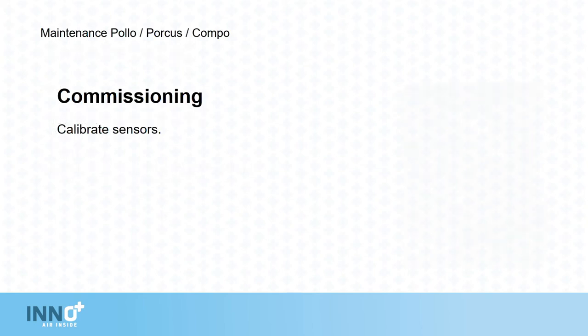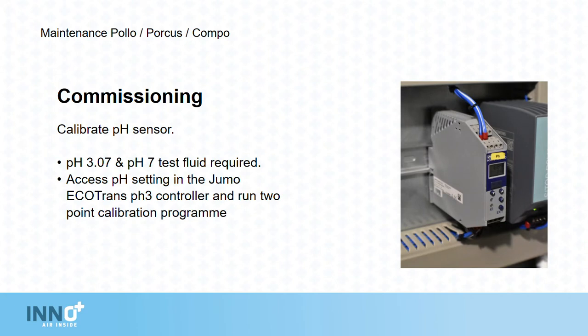Calibrate sensors. pH 3.07 and pH 7 test fluids are required. Access the pH settings in the Jumo ECOTrans pH3 controller and run a 2-point calibration program. This will require Inno code 110. Further information is available in the service handbook.